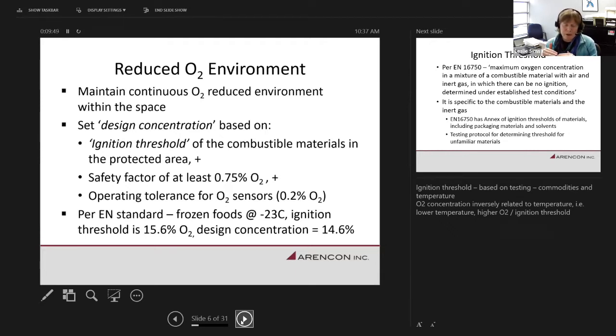But you want to set the design concentration of the system based on an ignition threshold. An ignition threshold, I put it in italics similar to our codes, is a defined term that comes from the European standards. The ignition threshold is established through testing, and it's related to the materials within the protected area. So it's different for different types of environments. An IT room would have a different concentration than, say, a warehouse with packaging materials. The ignition threshold is where we cross over between starving the fire and allowing it to grow. That's the threshold that we don't want to cross.